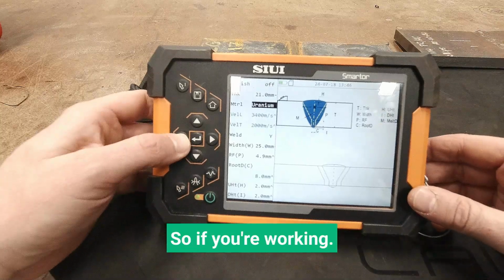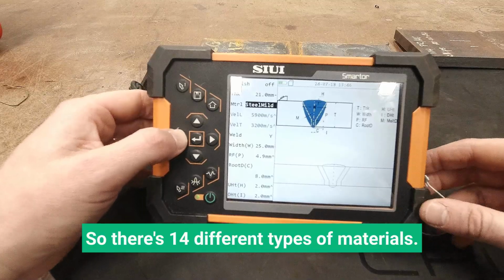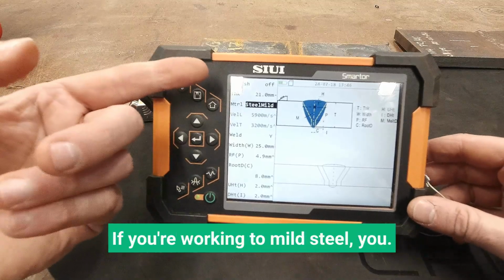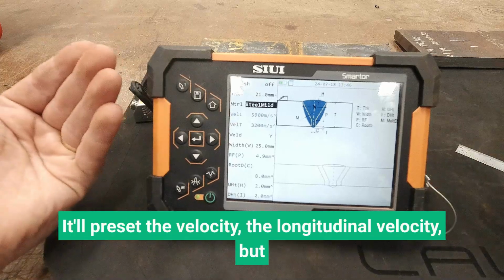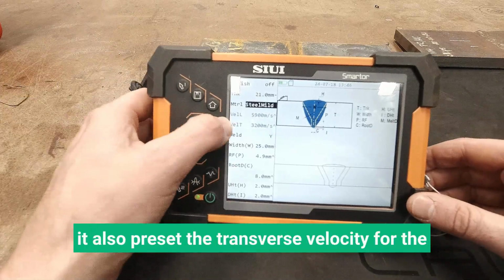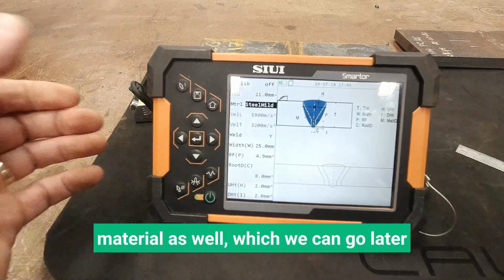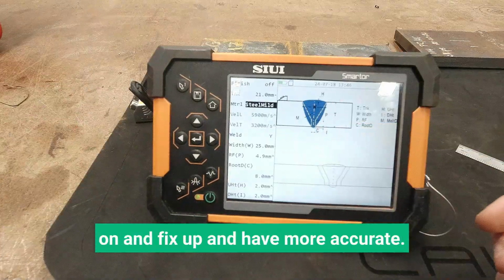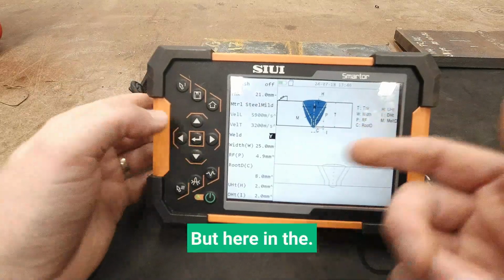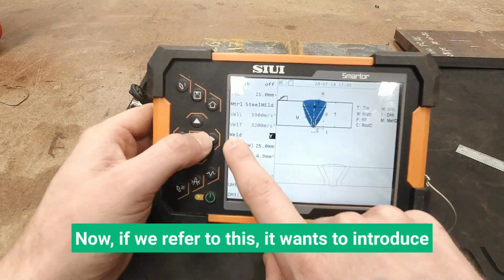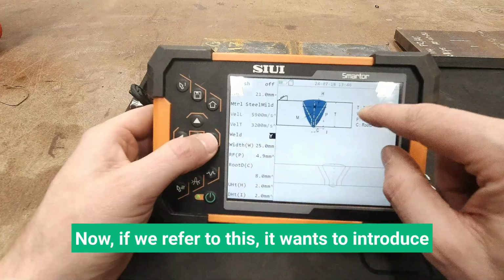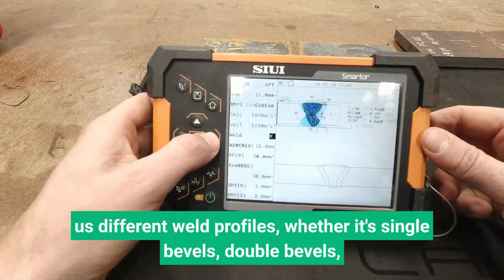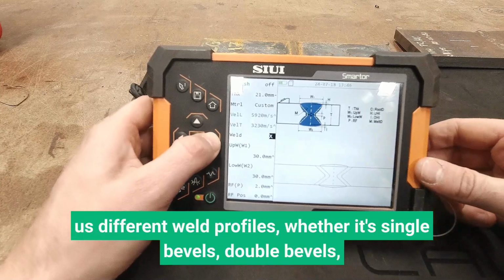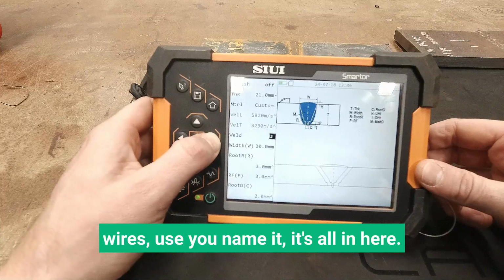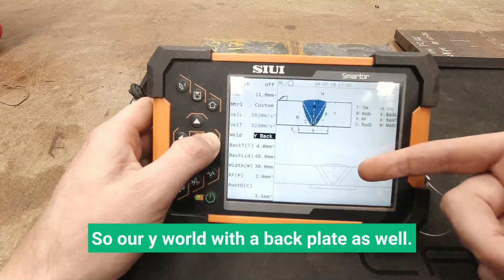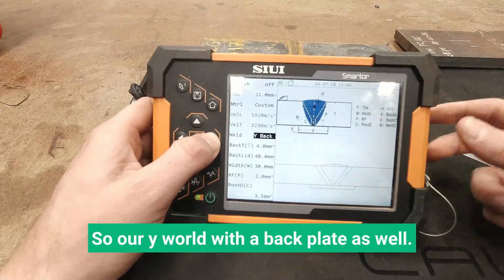There's 14 different types of materials. If you're working with mild steel, it'll preset the longitudinal velocity, but it also presets the transverse velocity for the material as well, which we can go later on and fix up and have more accurate. But here underneath the weld, it wants to introduce us to different weld profiles, whether it's single bevels, double bevels, Ys, Us, you name it. It's all in here. So a Y weld with a back plate as well.